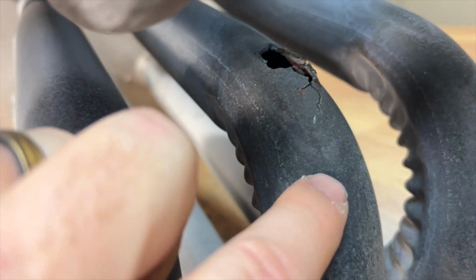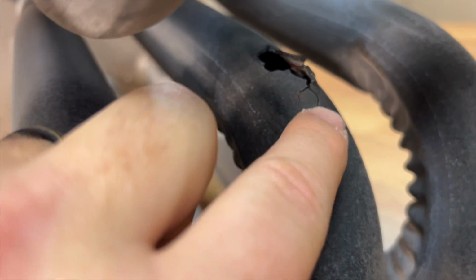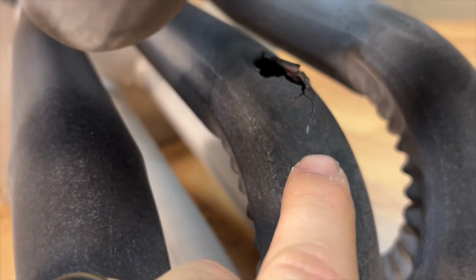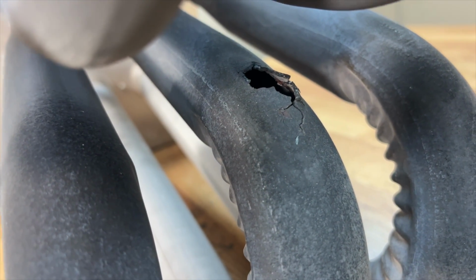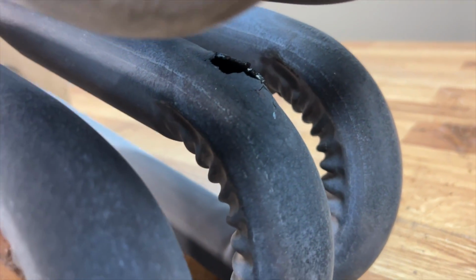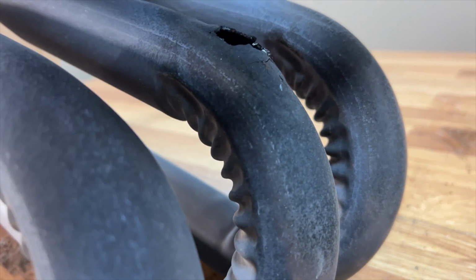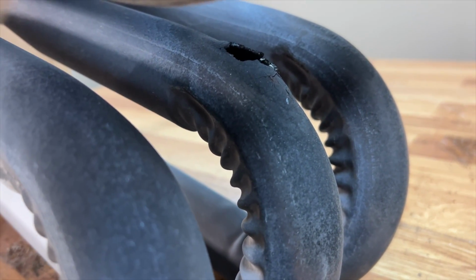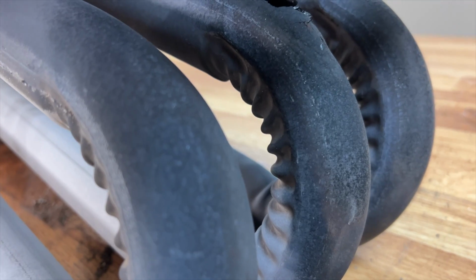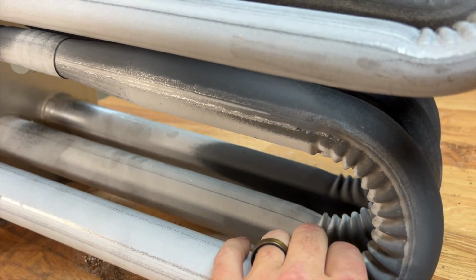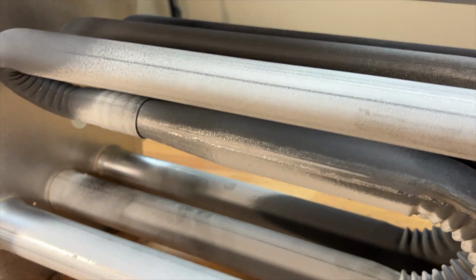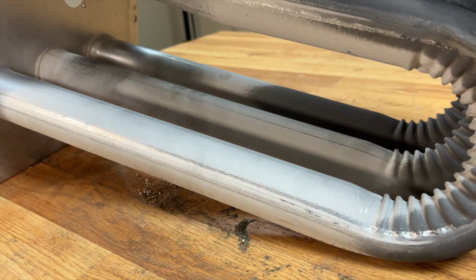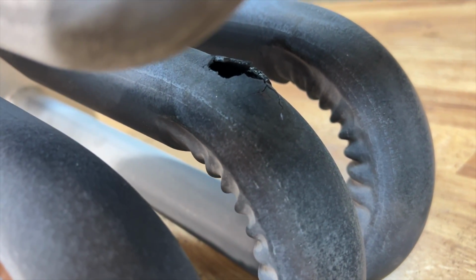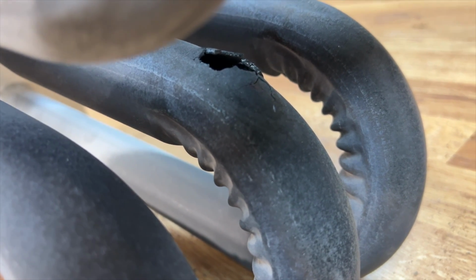And basically, over time, as it was hitting that spot, this was probably a hot spot, it just burned a hole right through it. So when you have something like that, definitely shut off that furnace. You need a new heat exchanger, you need a new furnace, whatever. But yeah, we were able to get a new heat exchanger for this one. I think we changed the heat exchanger. Well, that's why I have it. But yeah, that's an extreme case, okay? These are not common. Let me show you a big crack.